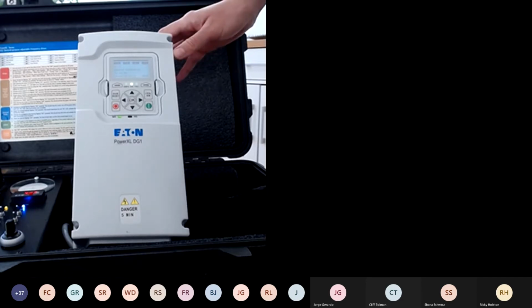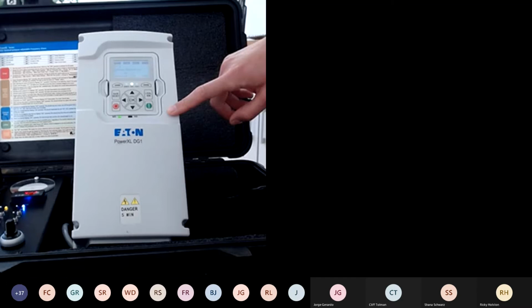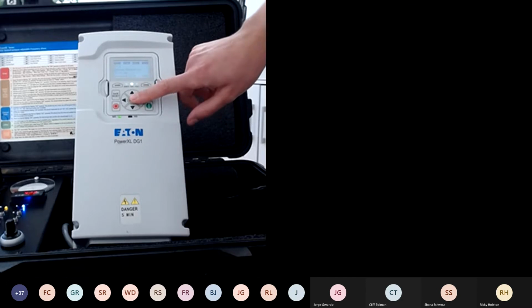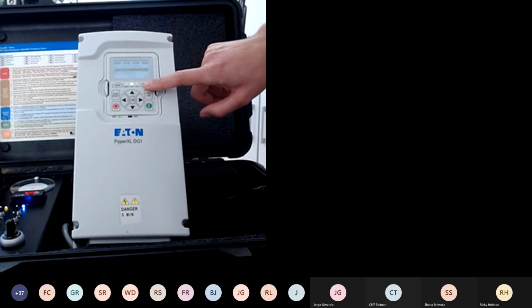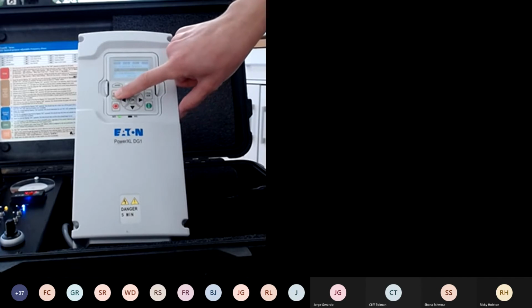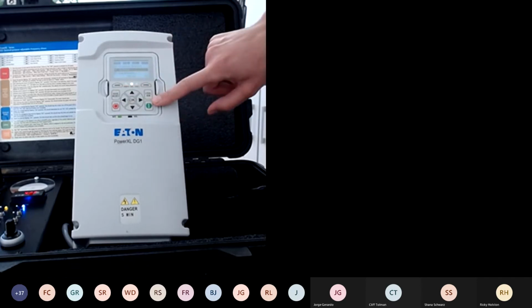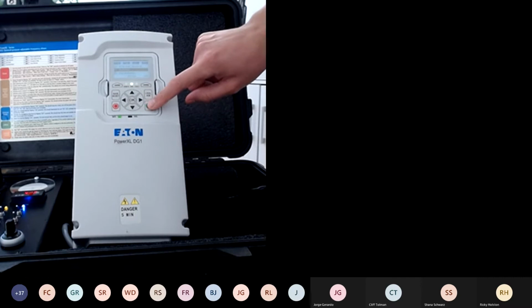So right now we're controlling the VFD and the motor through keypad control. We can adjust the speed by going up and down the arrow. Let's see if we can go back here to the menu. Back. And change this to remote control.